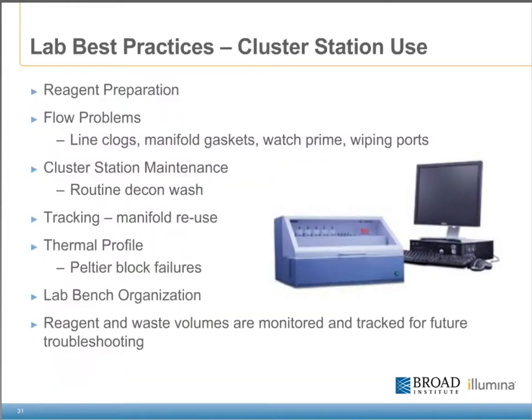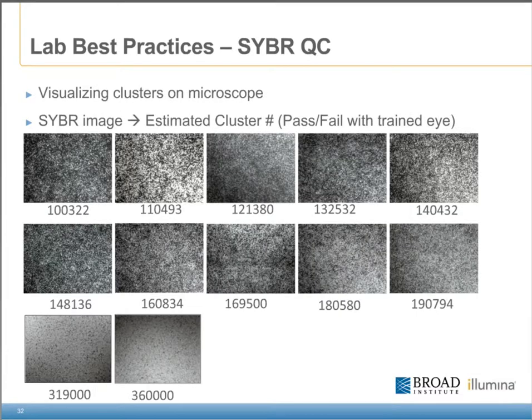It's pretty clear that introducing variation earlier in the process can affect your cluster counts. Automating most of this process has helped us to alleviate the effects of small-volume pipetting and user variability. From qPCR to strip tube generation, everything in our process is automated. We also store denatured libraries for reuse in case we need to create more data for a sample without introducing the variation seen in replicates. Other lab practices include ensuring that cluster stations undergo routine decon washes at least once per week, as well as our reagent tracking system and verifying proper flow on the cluster station.